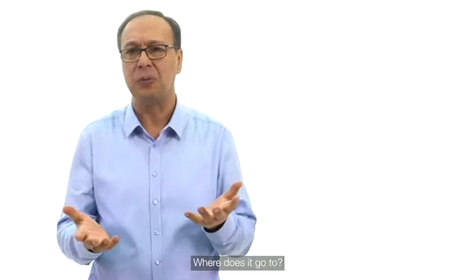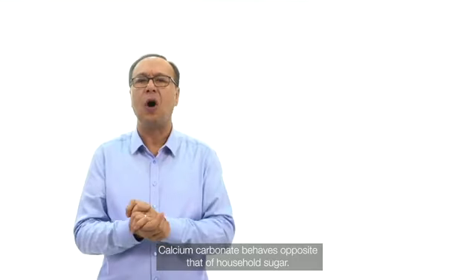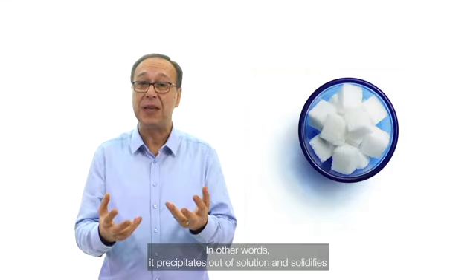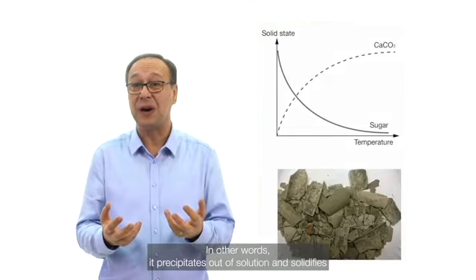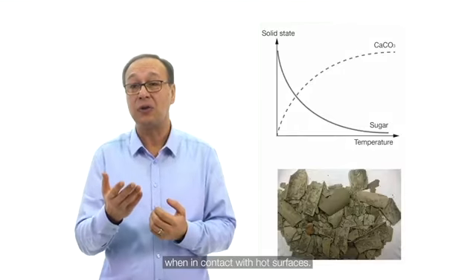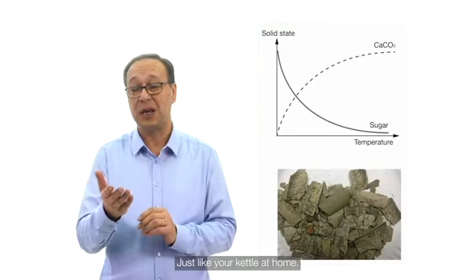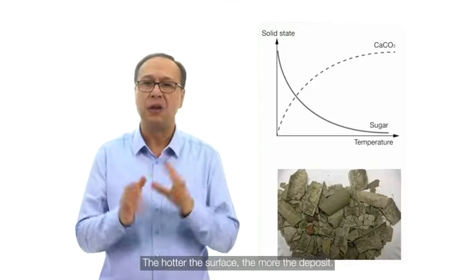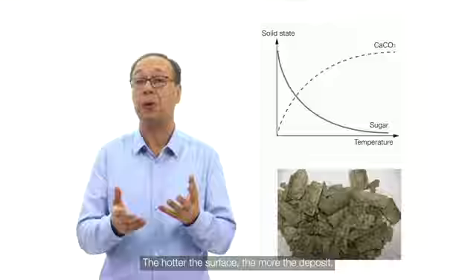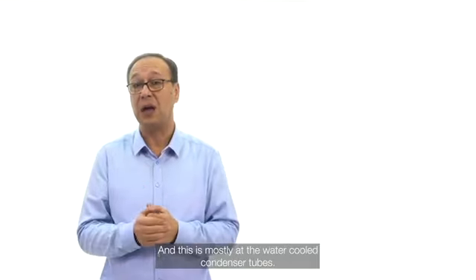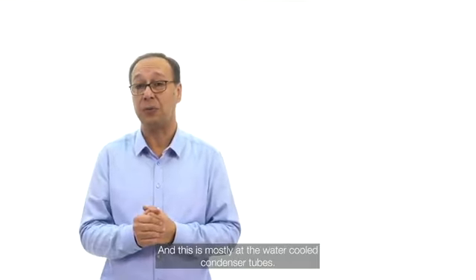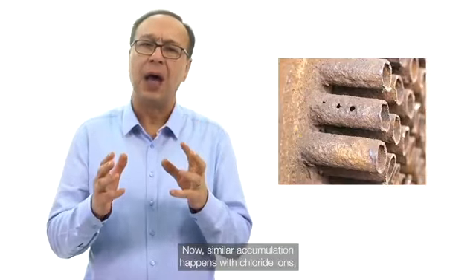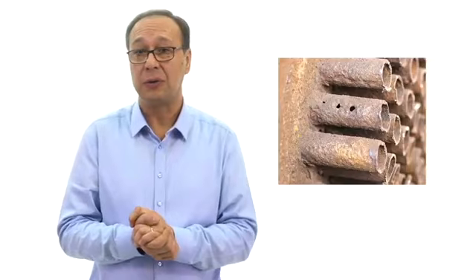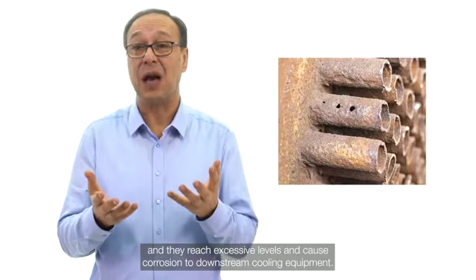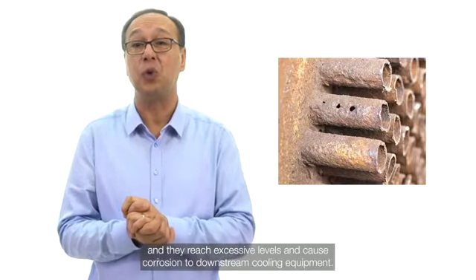Where does it go to? Calcium carbonate behaves opposite that of household sugar. In other words, it precipitates out of solution and solidifies when in contact with hot surfaces, just like your kettle at home. The hotter the surface, the more the deposit. And this is mostly at the water-cooled condenser tubes. Now, similar accumulation happens with chloride ions, and they reach excessive levels and cause corrosion to downstream cooling equipment.